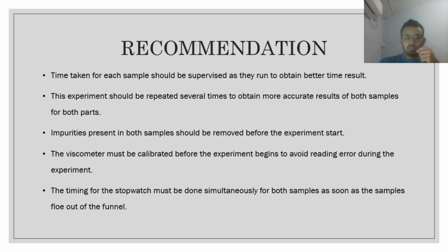Third, impurities present in both samples should be removed before the experiment starts. Fourth, the viscometer must be calibrated before the experiment begins to avoid reading errors during the experiment. And lastly, the timing with the stopwatch must be done simultaneously for both samples as soon as the samples flow out of the funnel.